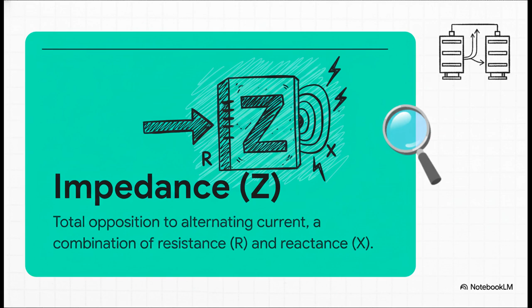And the formula that governs this is actually pretty elegant: the load on transformer 1 divided by the load on transformer 2 equals the impedance of transformer 2 divided by the impedance of transformer 1. See that? The numbers are flipped - 1 over 2 on the left, 2 over 1 on the right. That's the whole secret right there. It tells us that the load sharing is inversely proportional to the impedance.